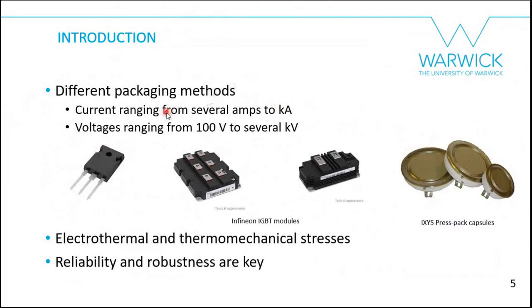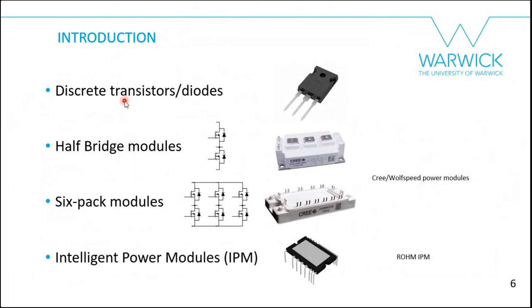There are different packaging methods because of different current and voltage ratings. Current ratings go from several amps to kilo-amps — from a discrete TO-247 to a press-pack capsule of several thousand amps. Voltages range from 100 volts or less to several kilovolts. If you want to operate at five, six, seven, or eight thousand volts you have to maintain clearance and creepage distances. Devices are subjected to electrothermal and thermomechanical stresses, so reliability and robustness are key.